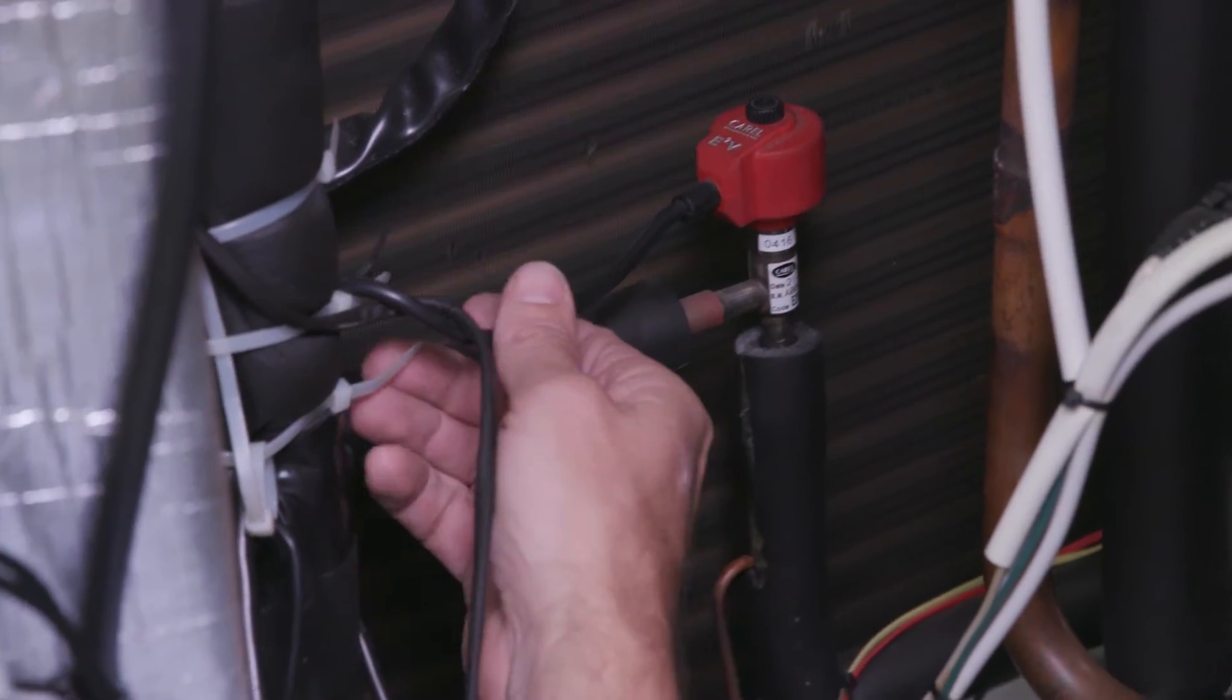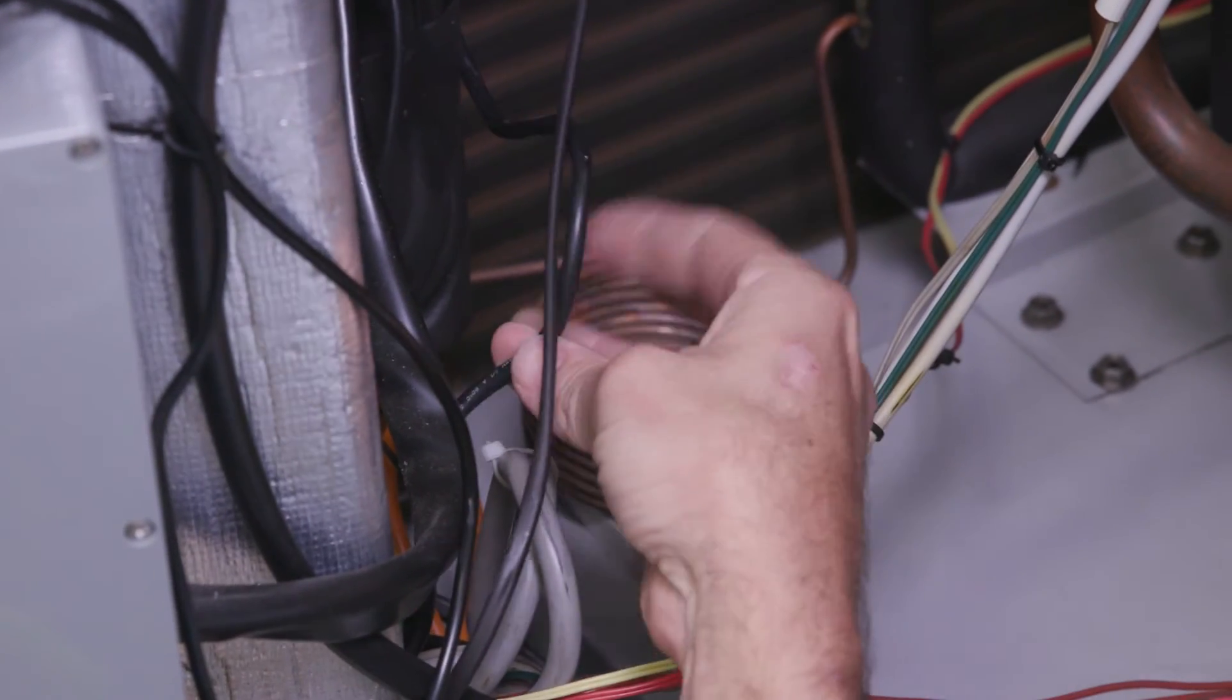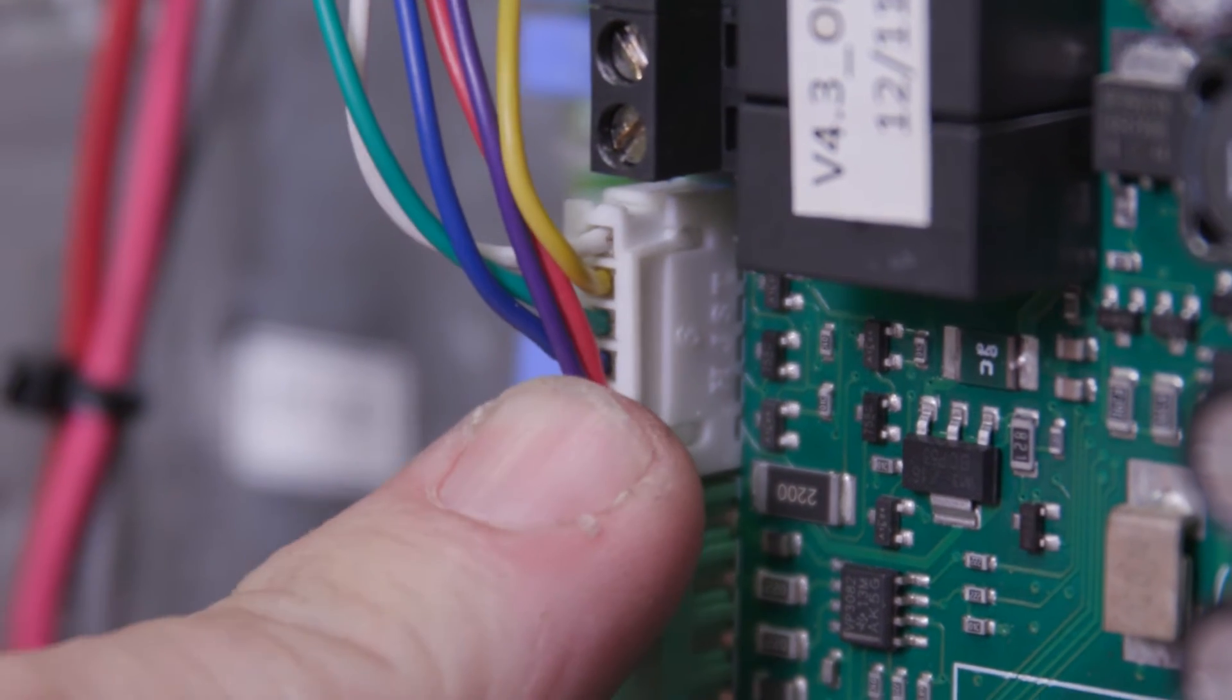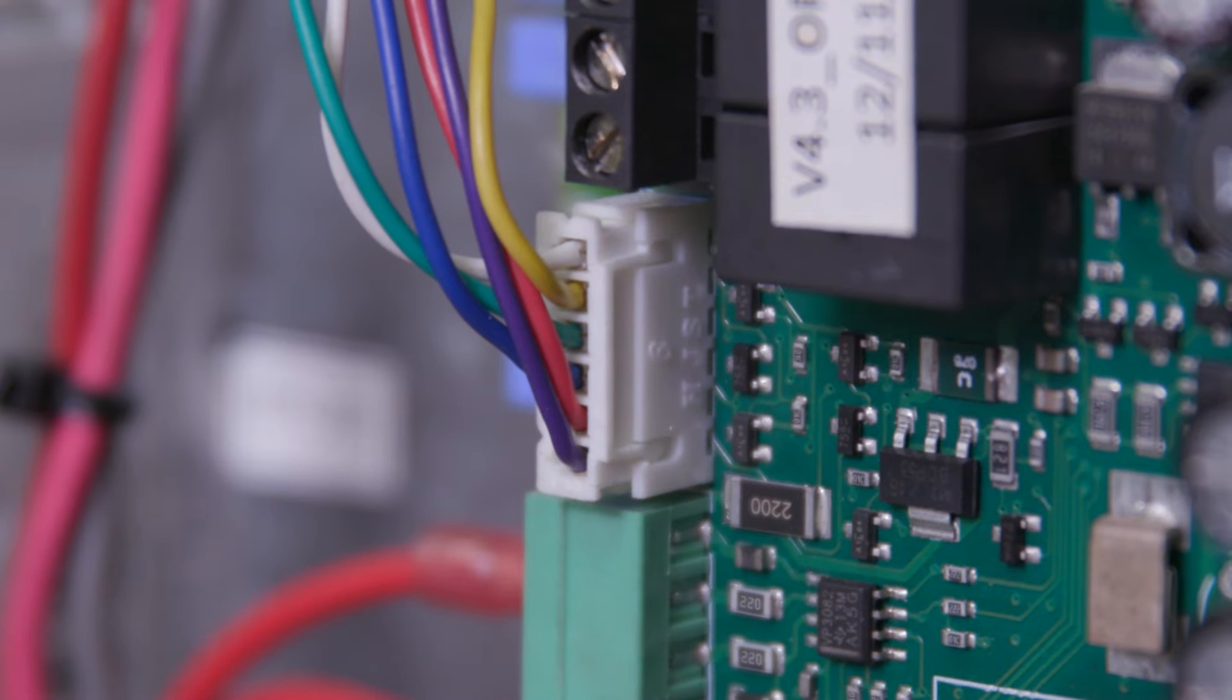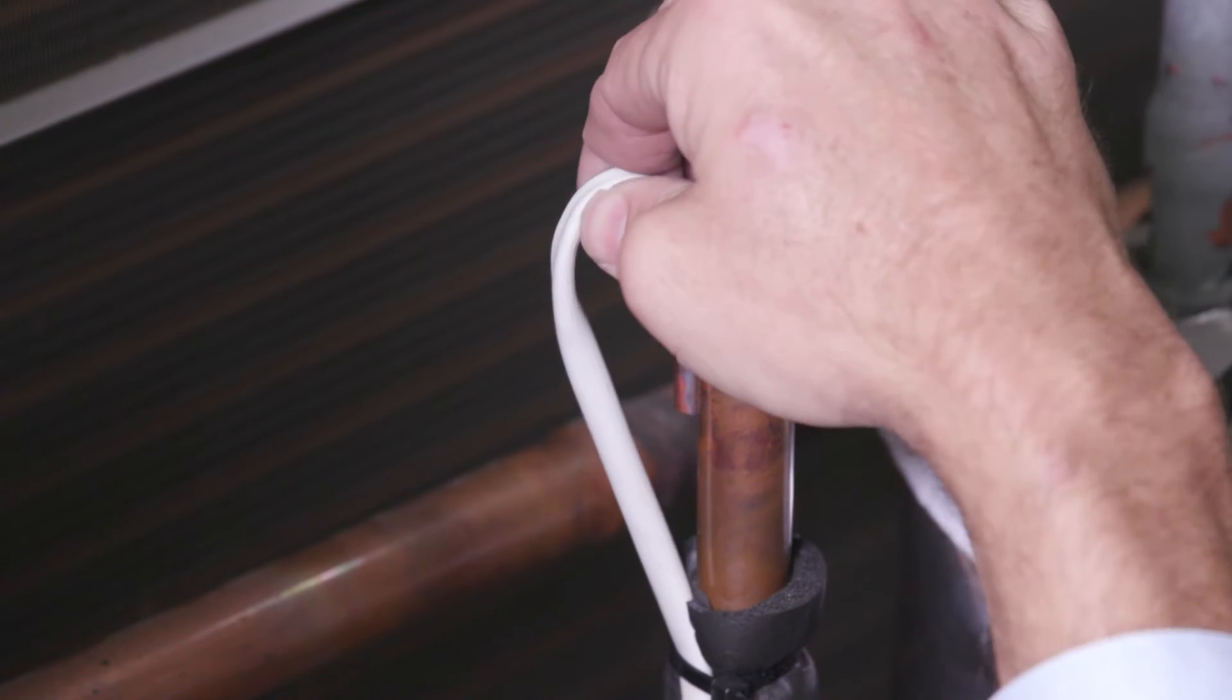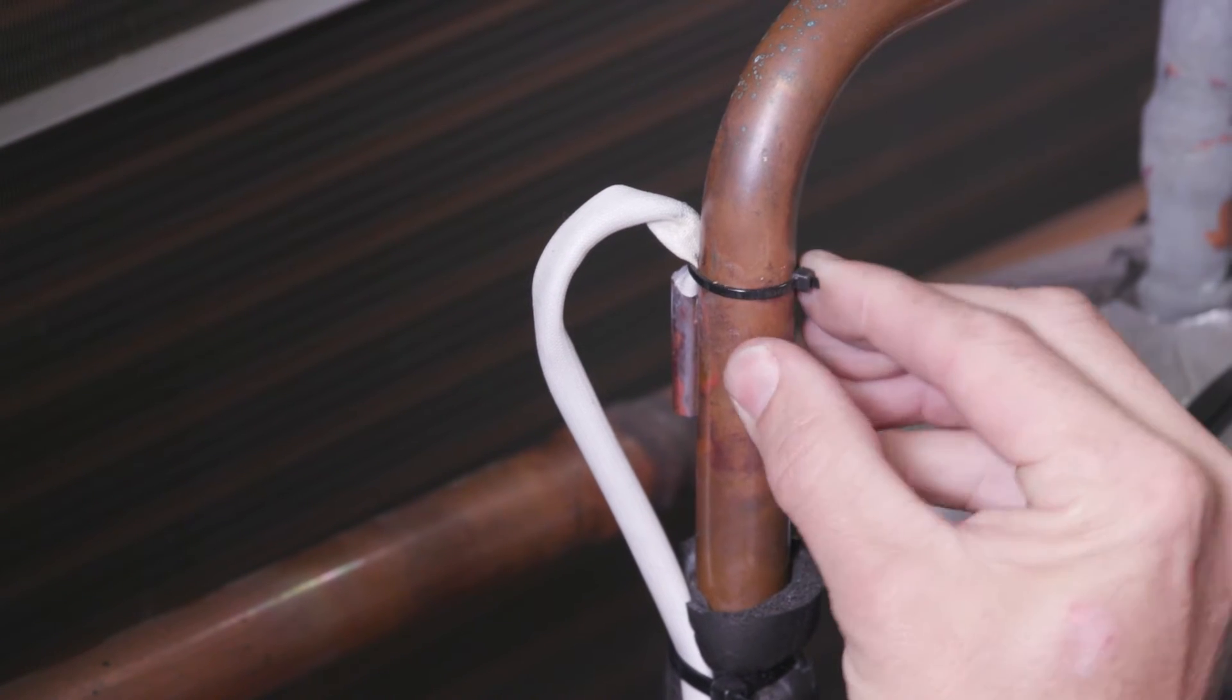Check the correct orientation of electronic expansion valve 1 and 2 as per the wiring diagram by tracing the cables. Ensure that the EEV plugs are firm and secure. Check that the sensor probes are tight and secure to the pipework. Use a cable tie to ensure secure connection if at all in doubt.